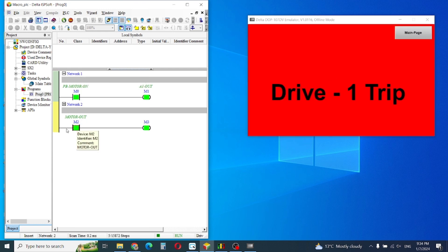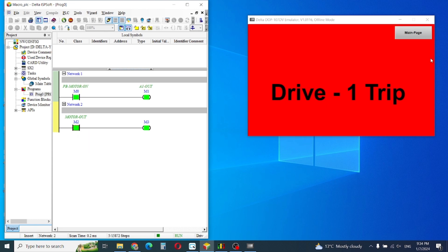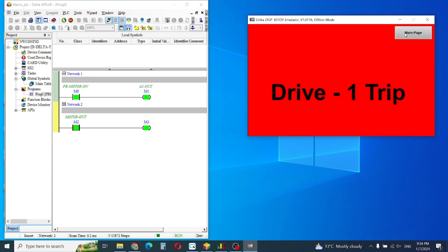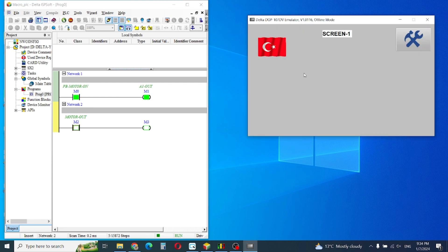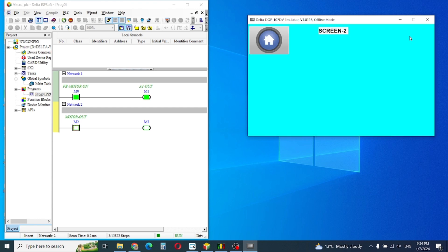Let's look at this. When our input is on, meaning our drive has tripped, I'll try to go to main page but I cannot go until I fix this problem through hardware. Now the problem is fixed, go to main page, and our main page will open.